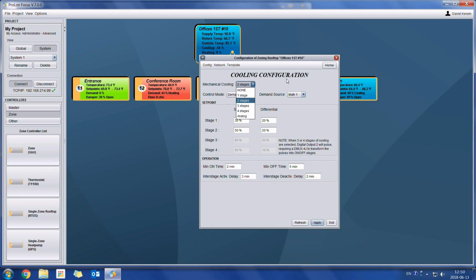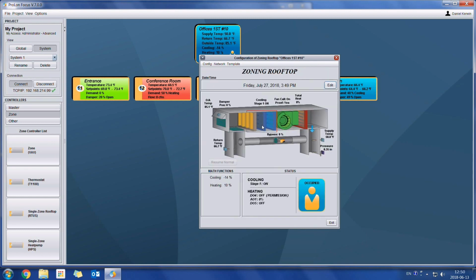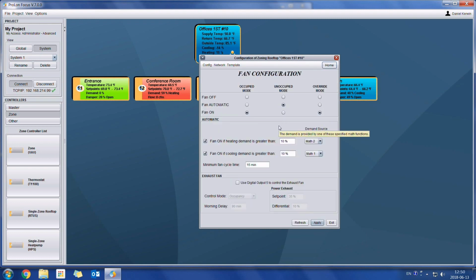Here we can choose how many cooling stages we have, and when those cooling stages turn on and turn off. So we can play with the on-off points right there. We also have minimum on time, minimum off time, as well as interstage activation and deactivation delays to avoid short cycling. If we take a quick glimpse at what the fan configuration looks like, once again just double click. Usually just looking at this menu is quite self-explanatory, so it can be very easy to configure it so that the fan will operate in the manner that we want.